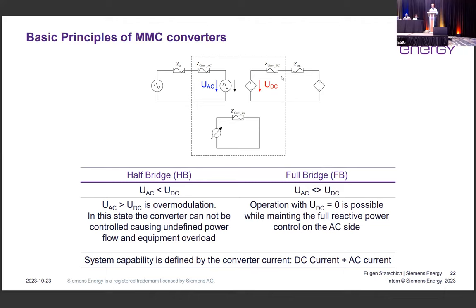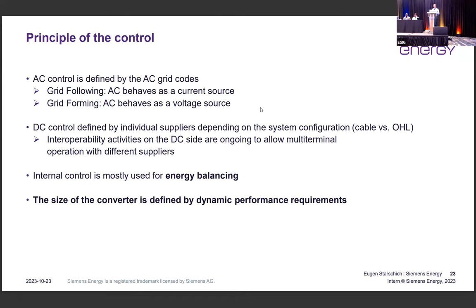And the biggest vendor-specific design is this internal control. That means I have a more or less independent control of the AC side and DC side, but I still need some balancing within the converter, and this is what is done within this control. This internal control is mostly used for energy balancing. As was shown at the beginning, the MMC has a distributed energy storage, and one of the major tasks is to balance all these small energy storages appropriately. This is what the internal control does.